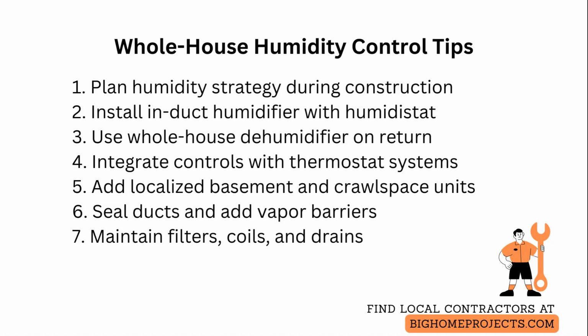Add localized units in basements and crawl spaces where ground moisture and poor ventilation create persistent damp spots. Use units rated for continuous operation and route condensate to a proper drain or pump. Include water vapor barriers, properly sealed ductwork, and balanced ventilation with heat recovery or energy recovery ventilators to manage fresh air without overloading your humidity system. Finally, set up a maintenance plan that includes regular filter changes, coil cleaning, drain line inspections, pad replacements for humidifiers, and seasonal checks to prevent microbial growth and preserve system efficiency.